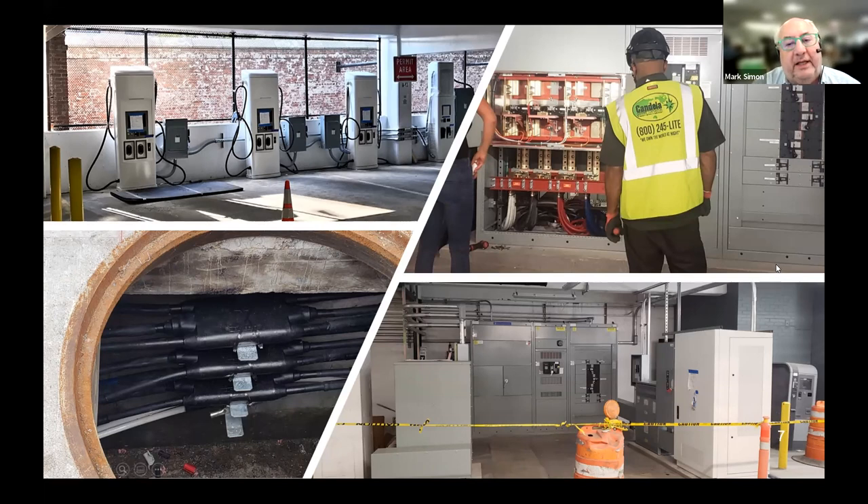This is the amount of equipment we needed to operate the four chargers and the space it took. As you're planning your parking facility, assume you may need this much space — there may be corners not used for parking where you won't lose as many spots to that. The utility has to inspect multiple times. Another issue — where the power comes to your site, the point of entry, you have to put on a property line box. We had challenges where construction folks felt the property line box was sufficient until we went to actually do the work, and it wasn't sufficient. We had to pull the property box and put in a bigger one.